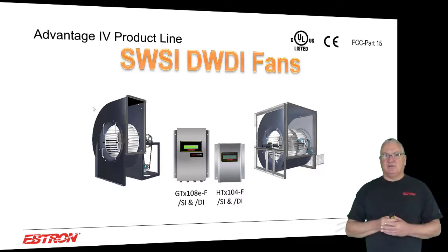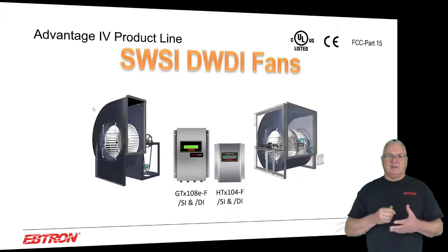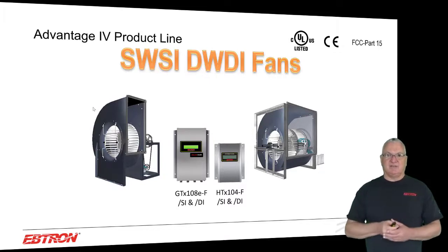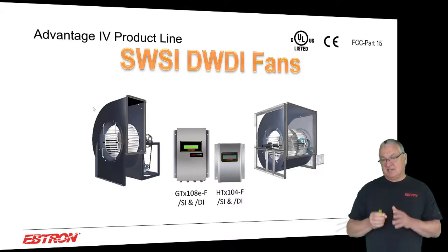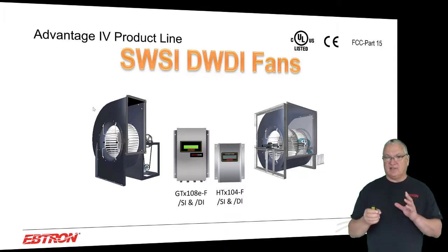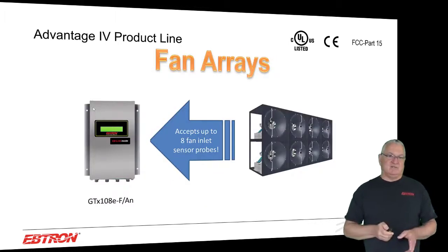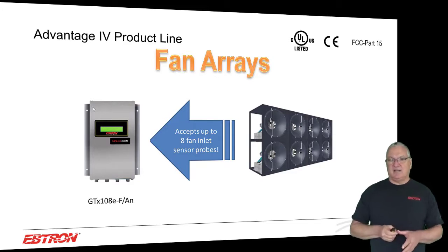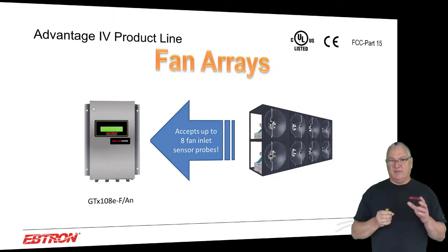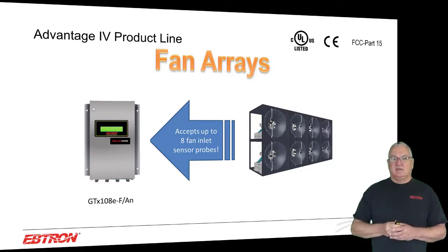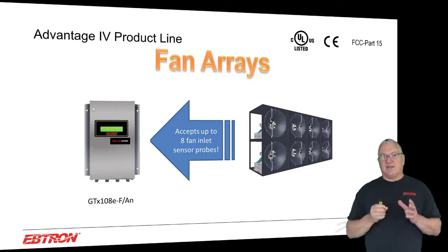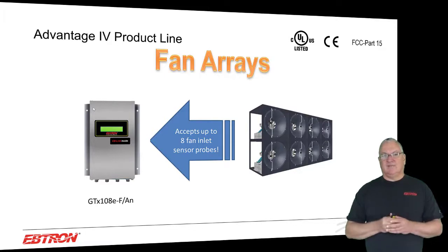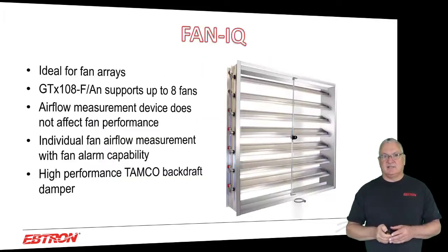Basically when we get into single and dual inlet fans, we have adjustable fan mounting brackets, which simplifies your installation. This is one case where there's not much difference between the gold and the hybrid except connectivity and EBLink, okay? So you have to really think about what you need there. The fan array is a gold series product. It's great. You can basically monitor up to 8 fans individually with this product, but the output is the total output of the fan. So it's good for fan arrays, and it's very cost effective on fan arrays.